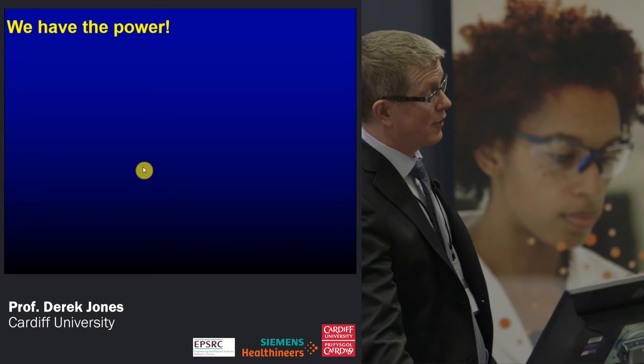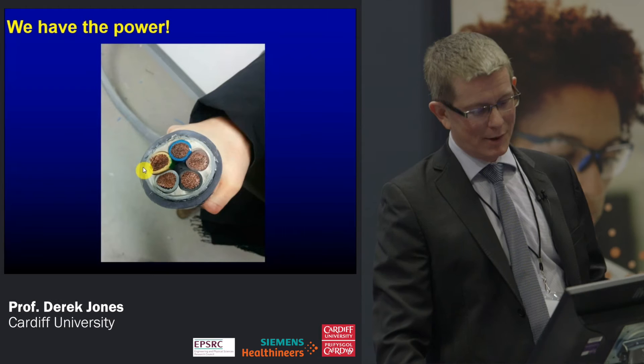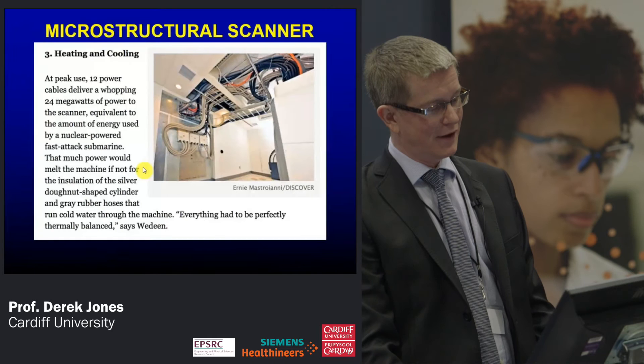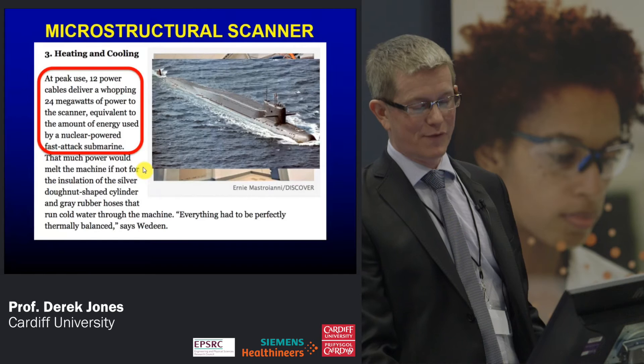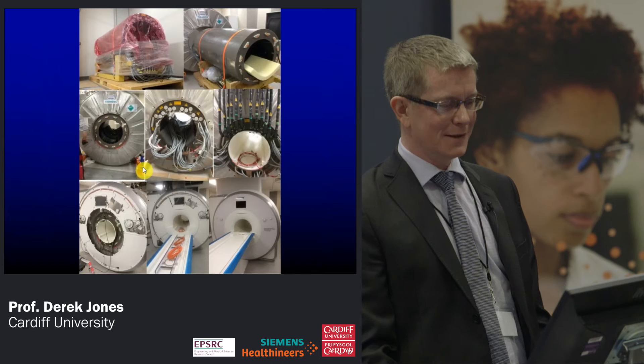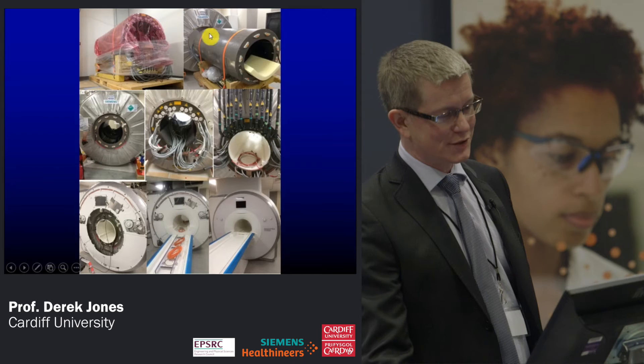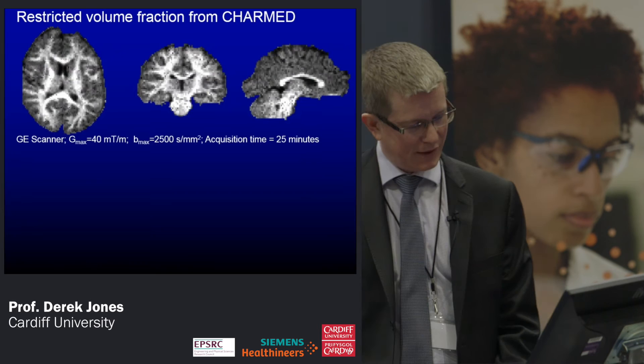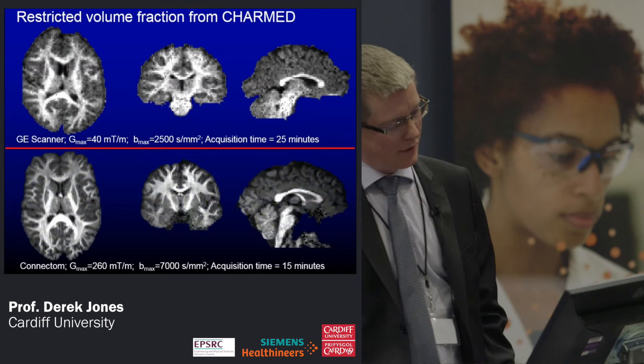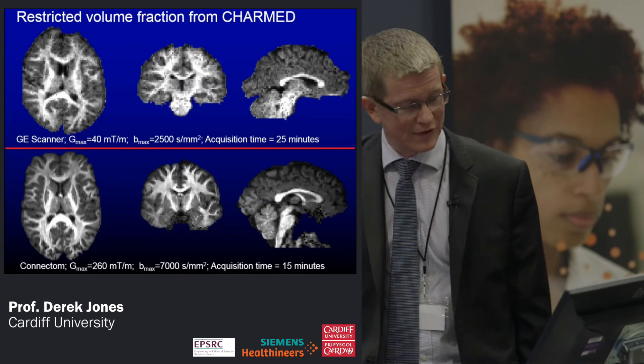Apart from those windings you need the power — we have the power. These are the power cables: four lots of 160 amps. We had a substation built for the centre. From that Discover magazine, I love the hyperbole: 'it delivers a whopping 24 megawatts of power to the scanner, equivalent to the energy used by a nuclear-powered aircraft carrier.' We show this to members of the public and they don't volunteer to go in. Just to compare: on our old scanner this was CHARMED data from a 25-minute scan at b=2500, and this was our first attempt with a 15-minute scan going up to b=7000 — the signal-to-noise is substantially better.